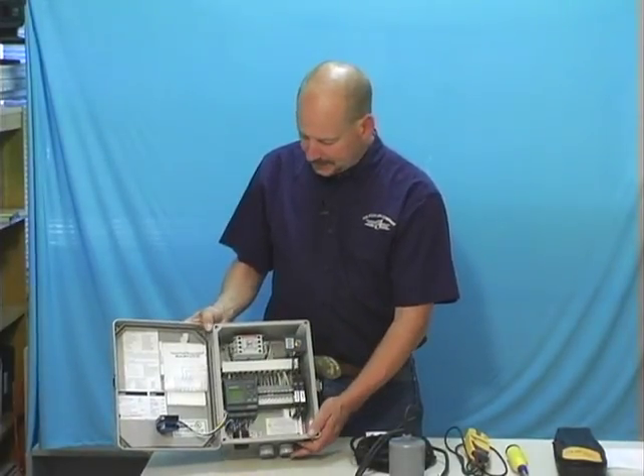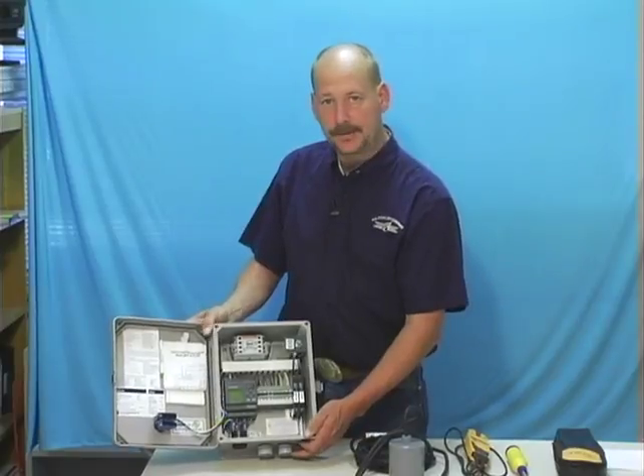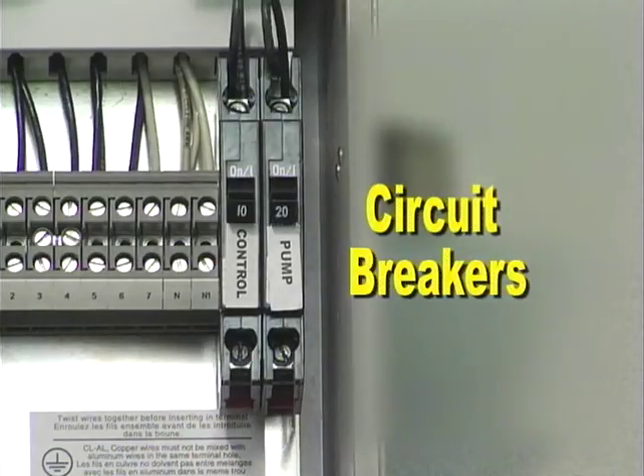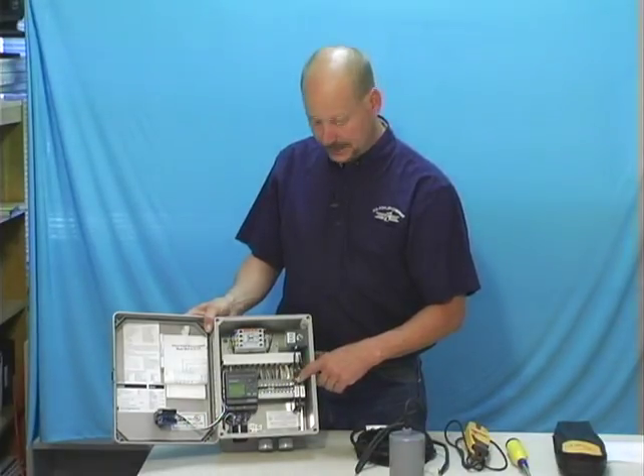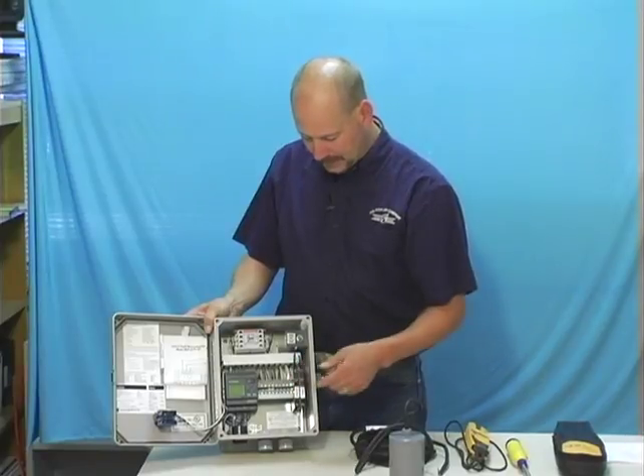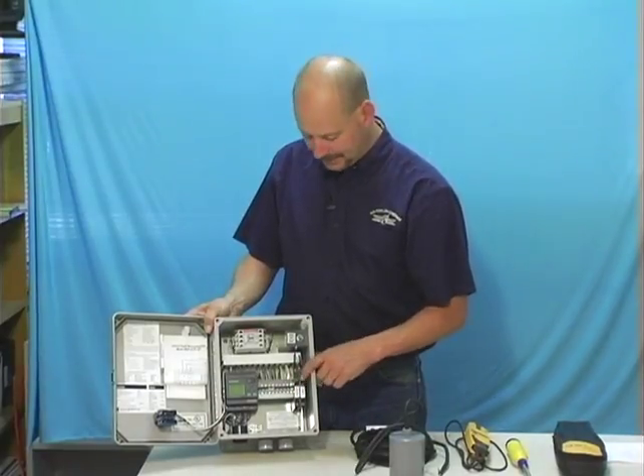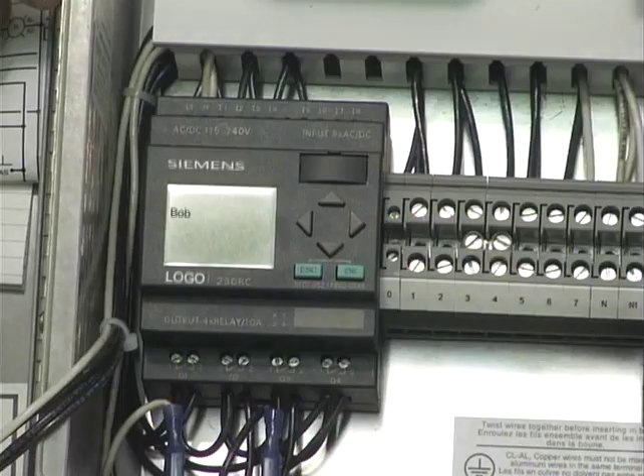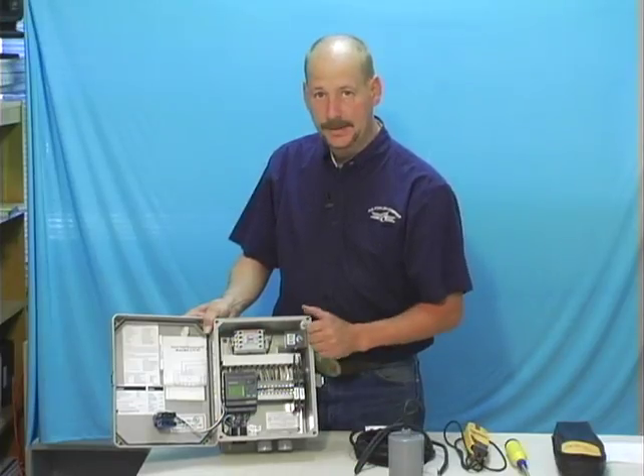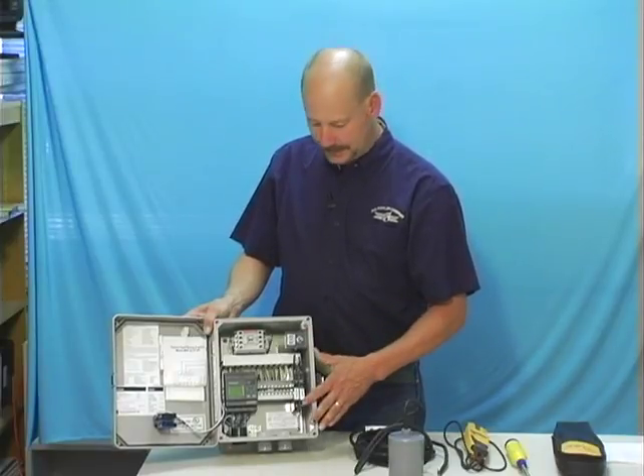Some of the key things, like I was saying before, that you need to look for in the control panels when you get up to them: see if the control breakers are off or the pump circuit breakers are off. If they are, then more than likely they've been tripped. Turn the control circuit breaker back on. You can leave the pump one off for troubleshooting and diagnostic work. Make sure that you do get an LED readout in the Siemens LOGO box. It could be a bunch of numbers that show up, or it could be the date and time. It all depends on what's going on with it.